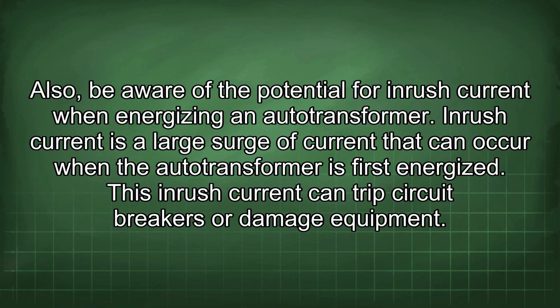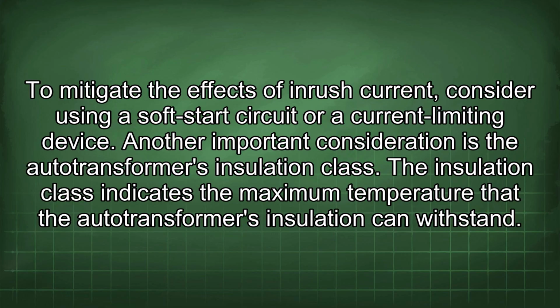Also, be aware of the potential for inrush current when energizing an autotransformer. Inrush current is a large surge of current that can occur when the autotransformer is first energized. This inrush current can trip circuit breakers or damage equipment. To mitigate the effects of inrush current, consider using a soft start circuit or a current limiting device.